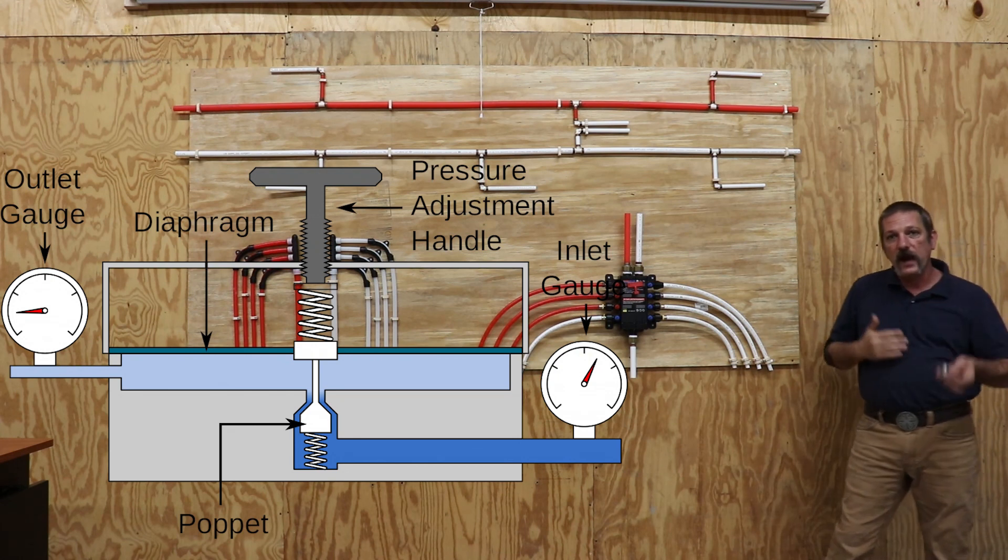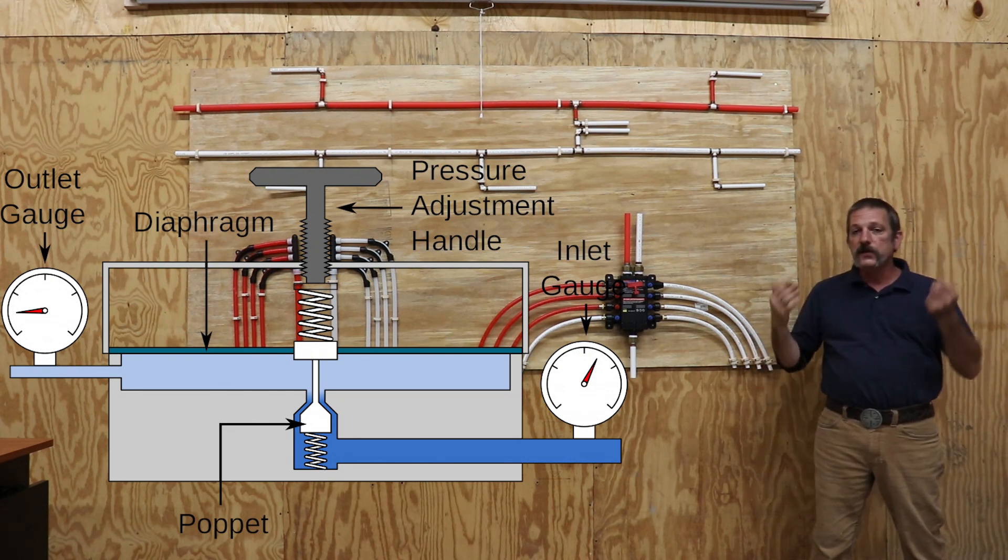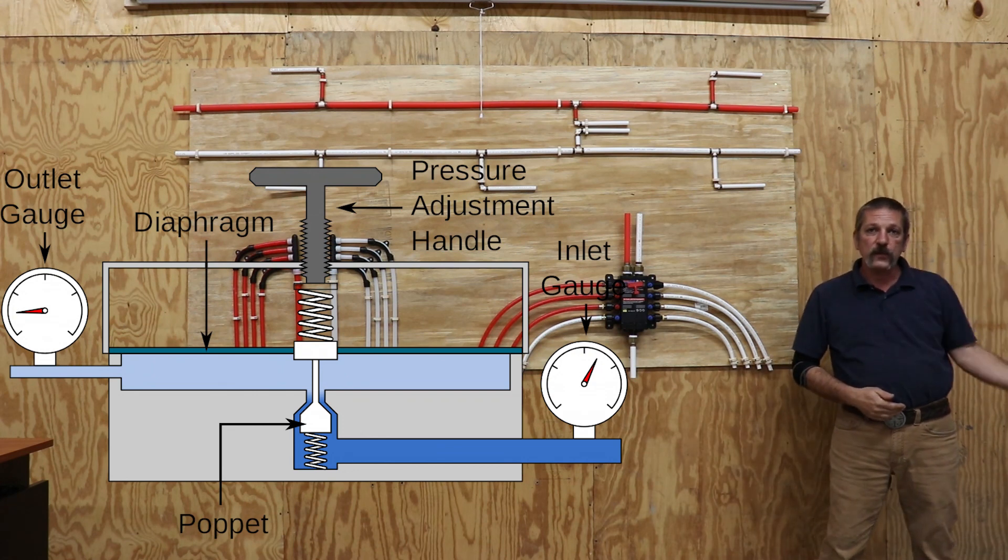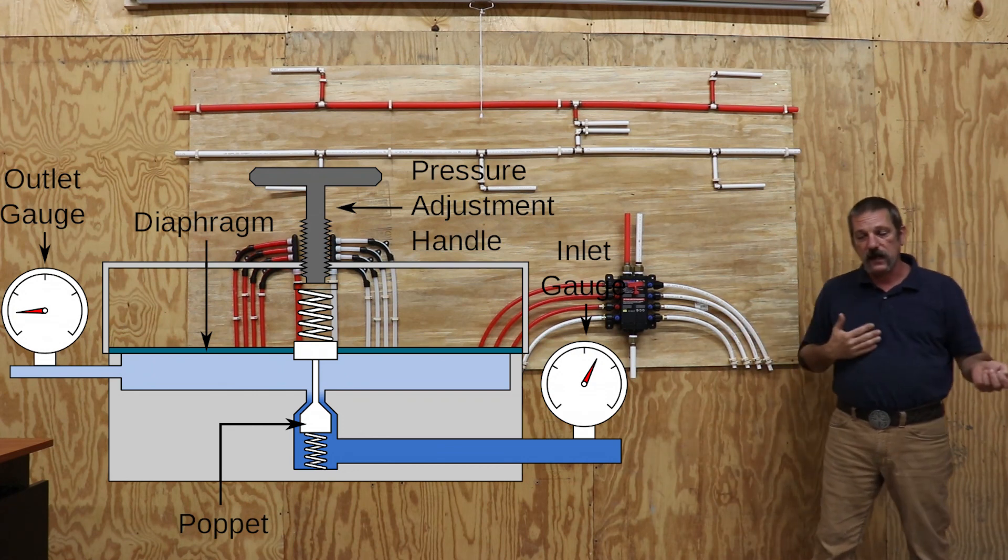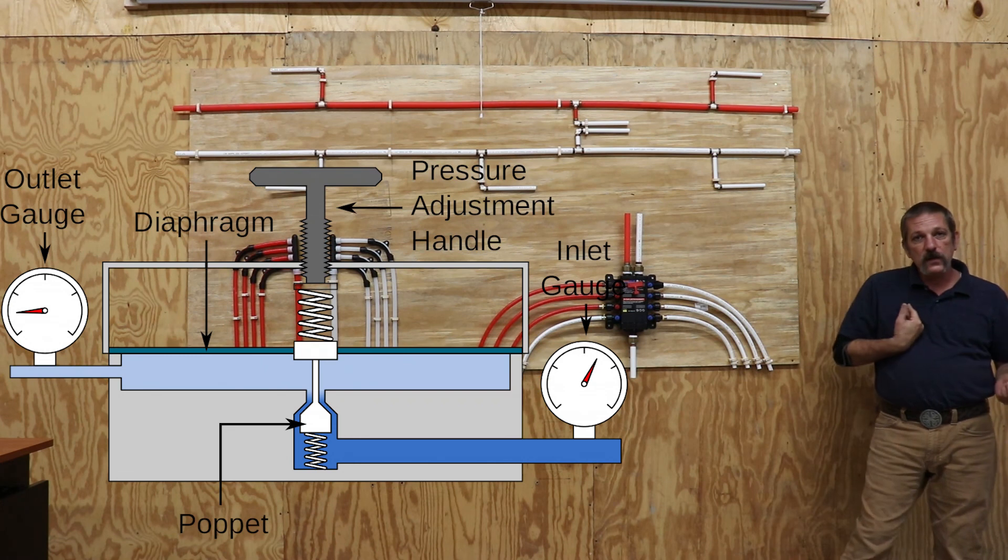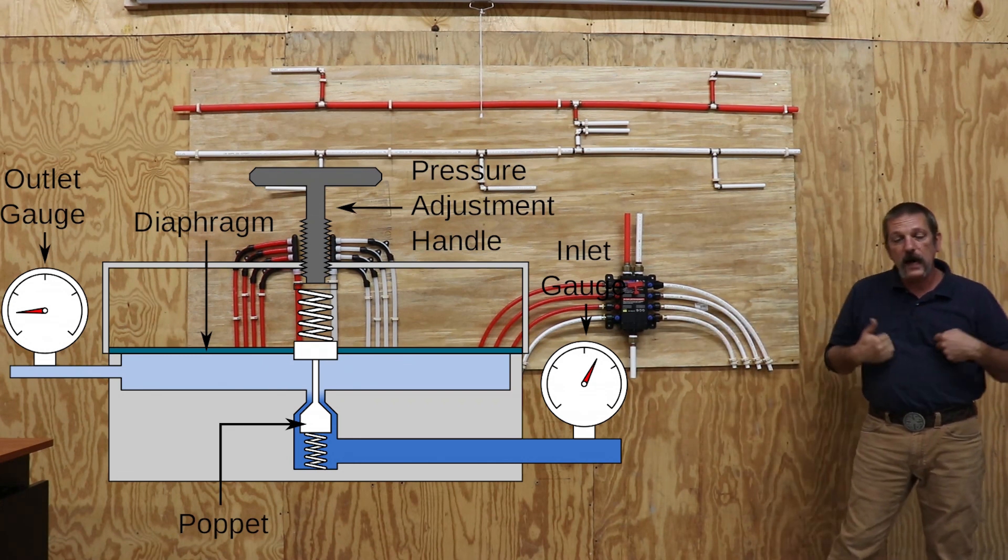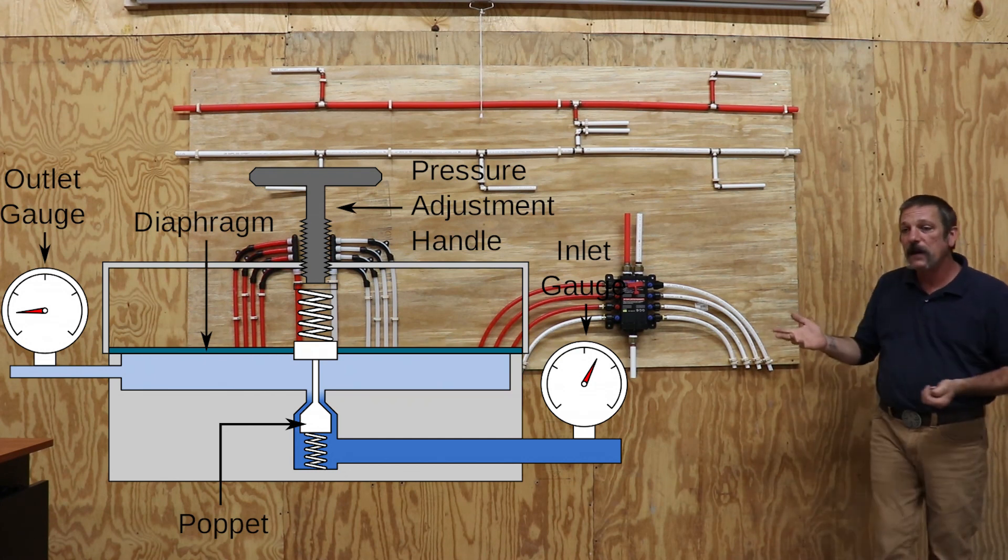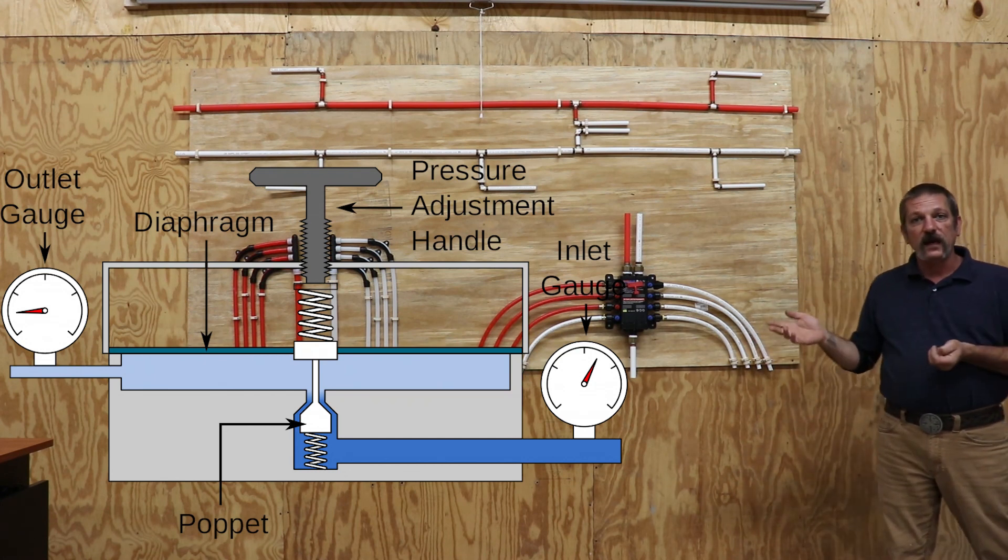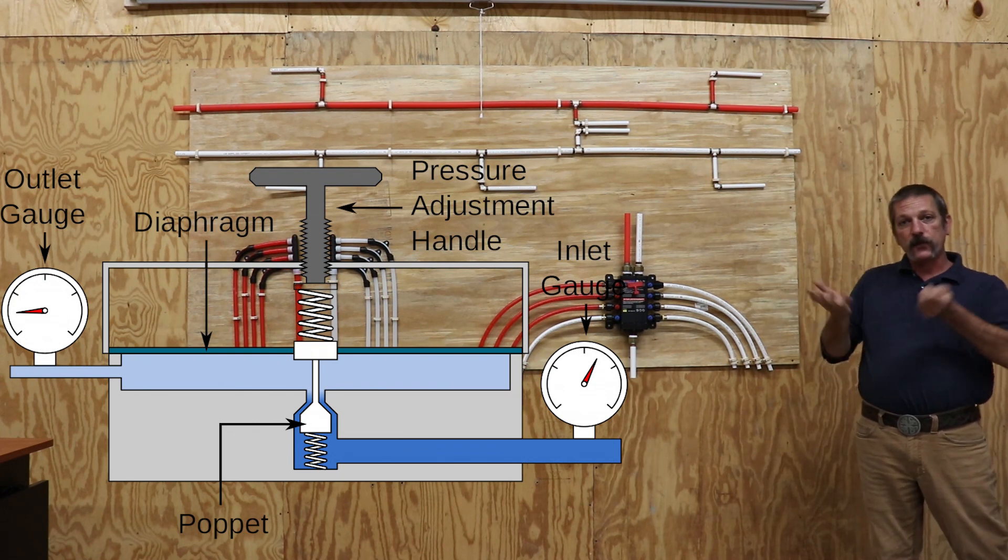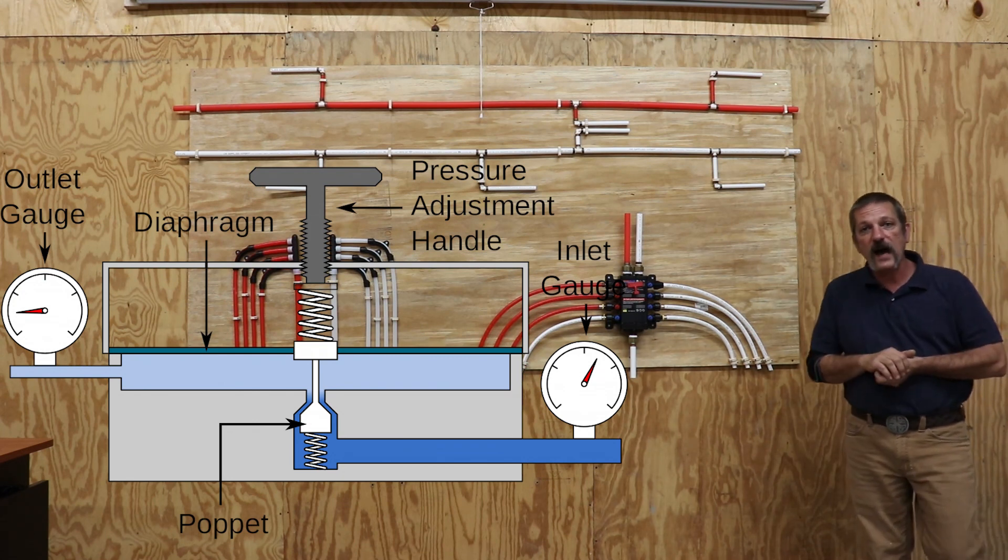Which is how it regulates the pressure. It's using the downward force of that spring and the water pressure to equalize itself. Now the ones we use work on the outgoing pressure. There are some that work on the incoming pressure. But it's the same basic thing. You've got the pressure from the spring and the pressure from the water pushing on that diaphragm. And when they balance out that poppet will close and that's how it works.